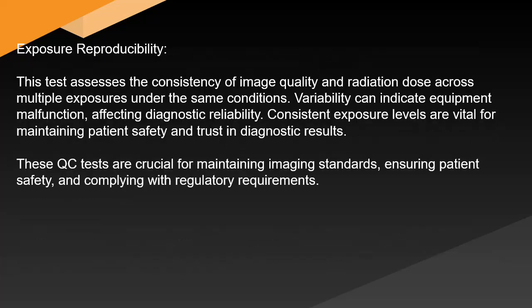Exposure reproducibility. This test assesses the consistency of image quality and radiation dose across multiple exposures under the same conditions. Variability can indicate equipment malfunction, affecting diagnostic reliability. Consistent exposure levels are vital for maintaining patient safety and trust in diagnostic results. These QC tests are crucial for maintaining imaging standards, ensuring patient safety, and complying with regulatory requirements.